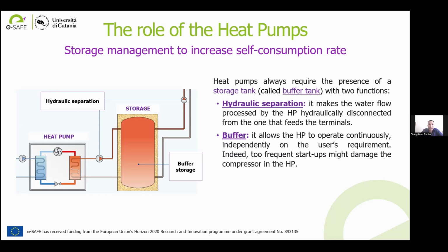Now, normally thermal systems with heat pumps work like that. They normally have a storage tank, because the storage tank is important as a hydraulic separator, to separate hydraulically the primary circuit and the secondary distribution circuit to the user, and also as a buffer tank, to avoid, for instance, too frequent startups of the heat pump. Designers of thermal systems should already know this rule of thumb. The minimum volume of the storage tank is around 10 to 20 liters of hot water per kilowatt of thermal power from the heat pump. This is what we normally do. But if we want to maximize this storage effect, we can increase the storage tank with respect to this minimum rule, let's say.